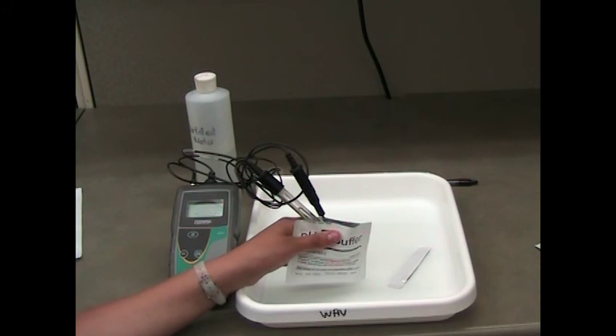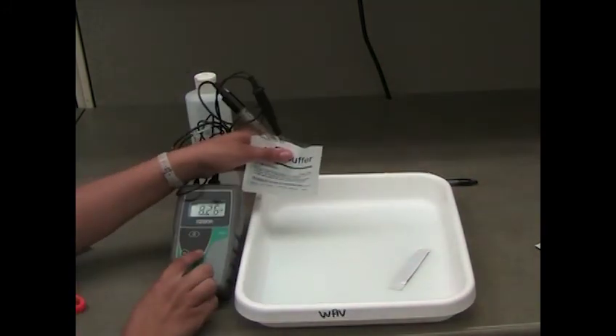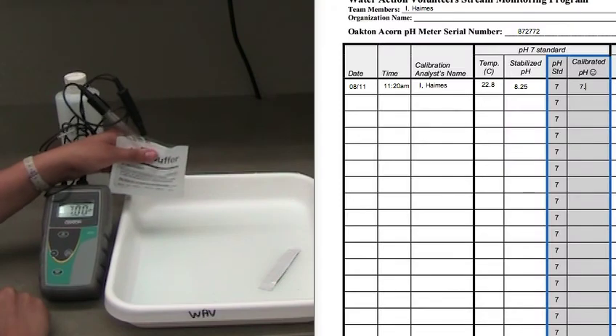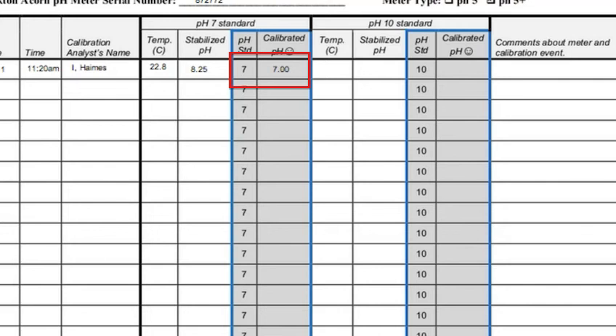When in calibration mode, the numbers will continue to flash. Press the enter key and record the calibrated pH value on the datasheet. Check that the calibrated value is within 0.2 of the pH buffer standard.